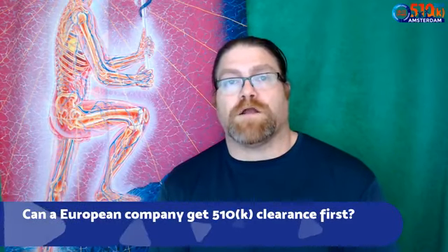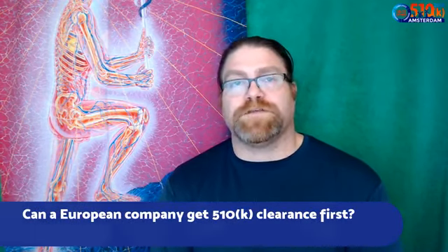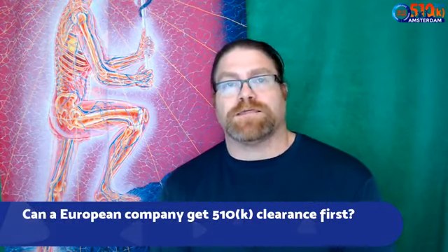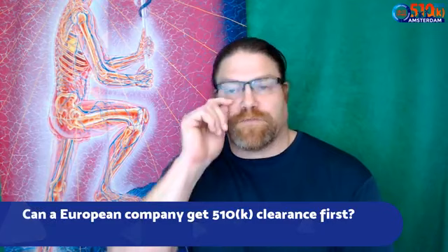But it might actually be an advantage to your company to get clearance in the US for some reasons. For instance, with the new MDR requirements, there's a lot more emphasis on gathering clinical data specific to your product, not to a competitor's product, and they're not accepting a lot of literature review approaches for companies. So you really need to get that clinical data on your product. Well, it can also be post-market clinical follow-up studies, not just pre-market clinical studies. So you could get a 510K clearance first, just for the purposes of gathering post-market surveillance data, so you can submit it to the European notified body for your CE marking. And that would be one approach that you can use. It's not the only approach, but it's an approach that may be used more and more as we see companies trying to comply with the new MDR.